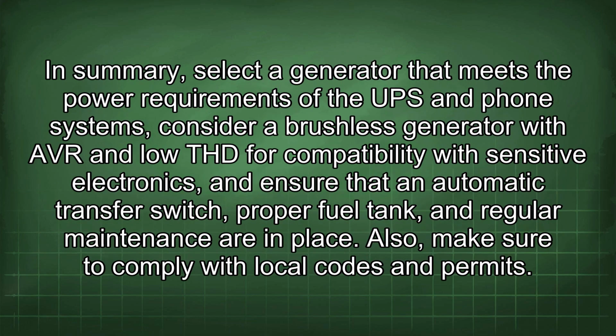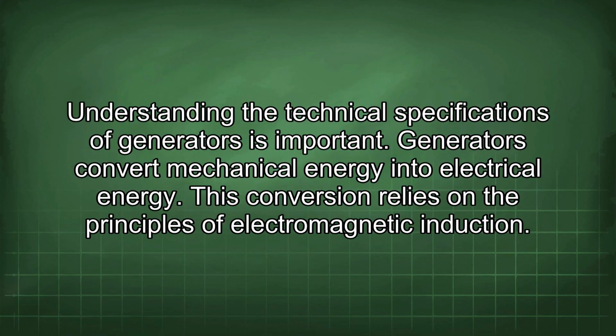In summary, select a generator that meets the power requirements of the UPS and phone systems. Consider a brushless generator with AVR and low THD for compatibility with sensitive electronics, and ensure that an automatic transfer switch, proper fuel tank, and regular maintenance are in place. Also, make sure to comply with local codes and permits. Understanding the technical specifications of generators is important.